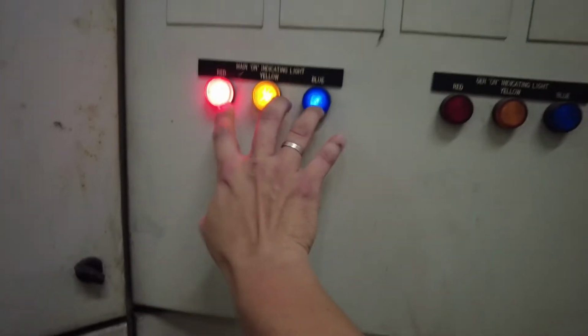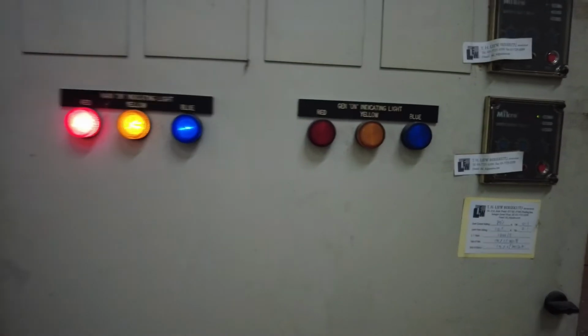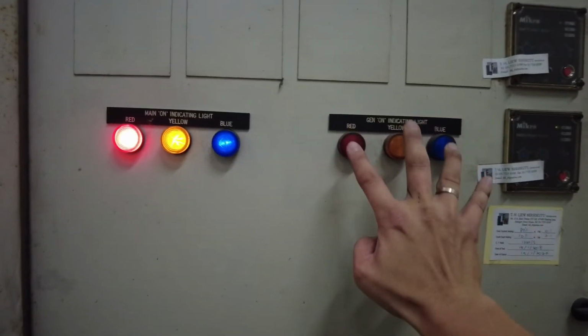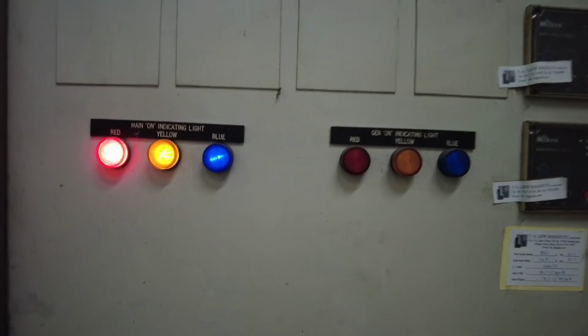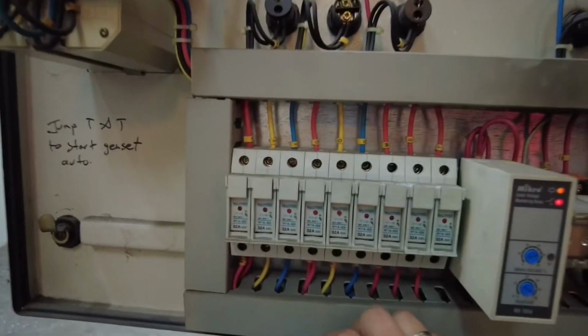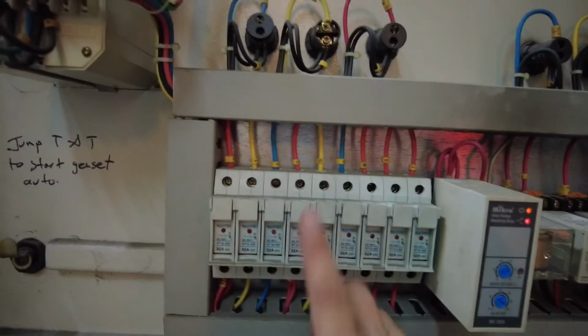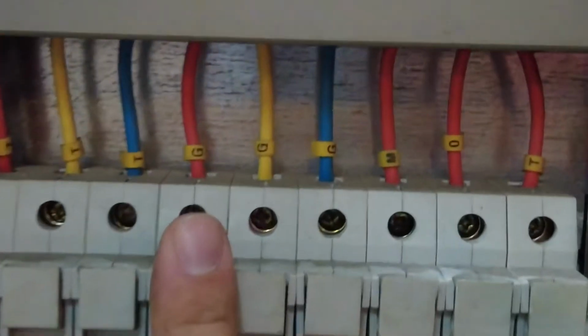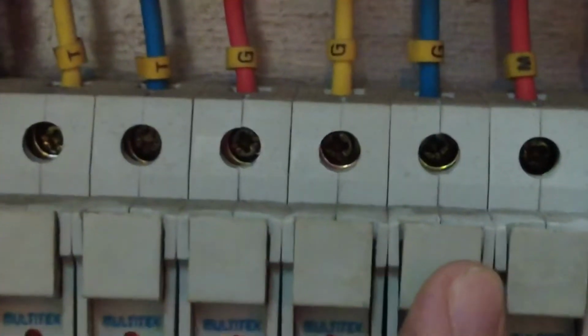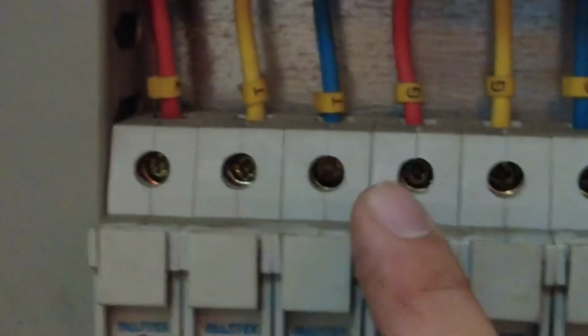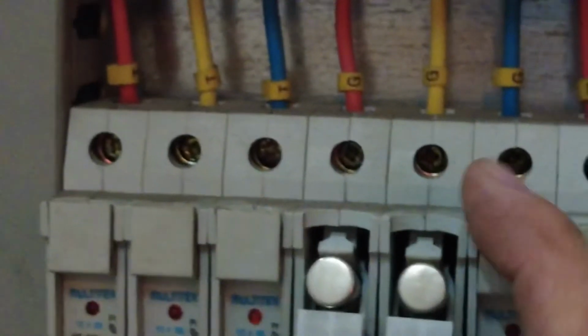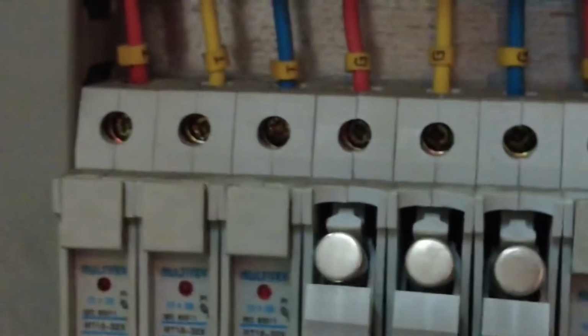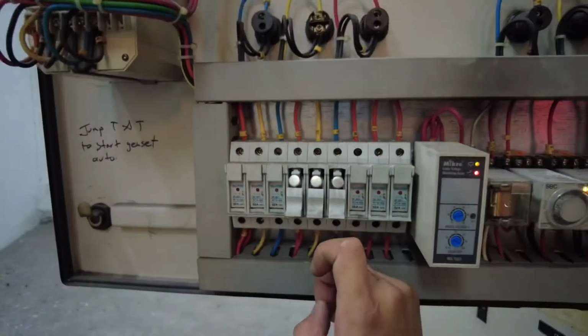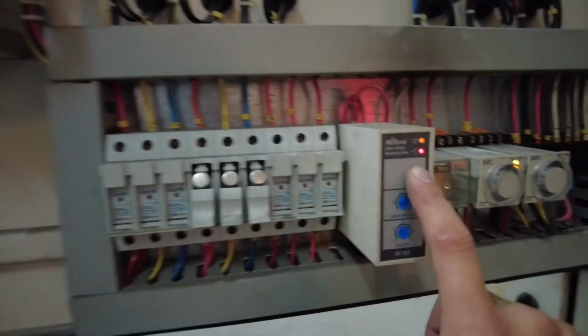Same also, the main supply is on, genset is off. Now we're going to make it happen to allow the genset to start automatically without going to the genset room. As usual, you must first locate which is the genset fuse, the one with the G. Red, yellow, blue. Take it out first. Then trigger the UVR relay.